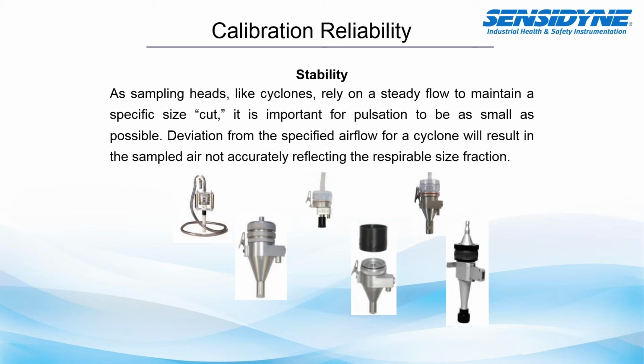Now, this is especially important when you're actually sampling using a cyclone for respirable dust or respirable silica. These sampling heads rely on a steady flow to maintain a specific size cut. It is important for pulsation to be as small as possible. Deviation from the specified airflow for a cyclone will result in the sampler not accurately reflecting the respirable size fraction. So in other words, if your flow rate deviates from that sampler's specified flow rate for the 4 micron cut point, which is the cut point for the respirable fraction, then it can actually either over-collect or under-collect the concentration at that particular flow rate.